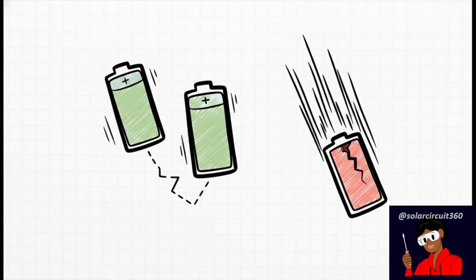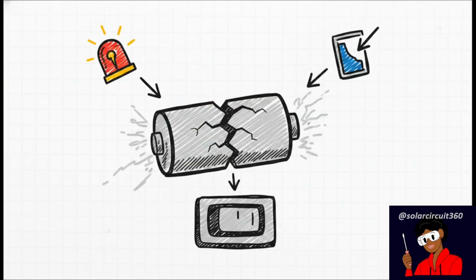The whole point of this test is figuring out the difference between normal voltage sag and a genuinely weak cell. Expecting your cells to stay perfectly identical under massive load is, frankly, just unrealistic. Normal, healthy cells are going to sag, for sure, but they'll generally move downwards together as a group. A truly weak cell, on the other hand, is going to drastically break away from the pack and just dive down all by itself. And that is absolutely crucial, knowing the real signs of actual cell deterioration.